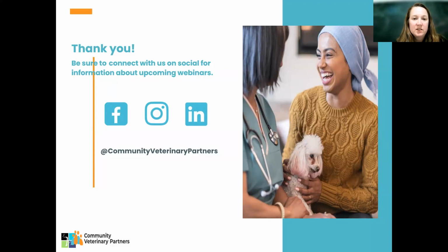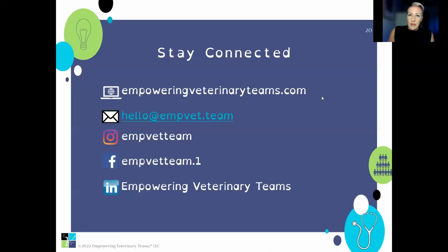So the question says there's no way to double check if there's a mistake, like you can with HR or temp, where you can double check. Okay. So it depends, and again, I'm not trying to avoid the question. It's really going to depend on what type of capnograph you have, if it's a side stream or an in stream, and just how that's actually measuring your end tidal CO2.